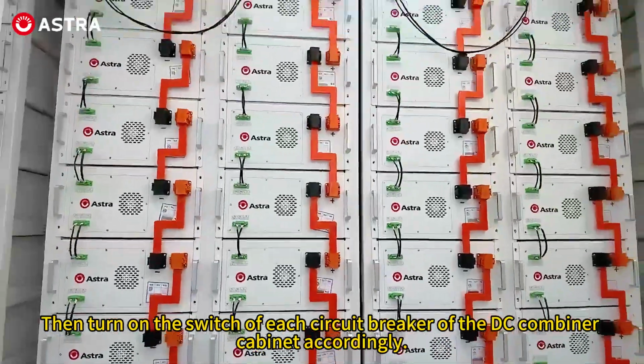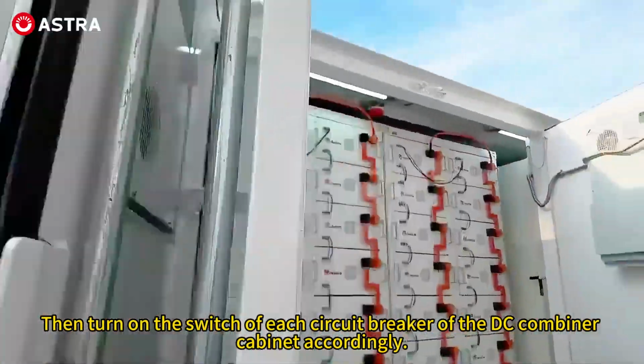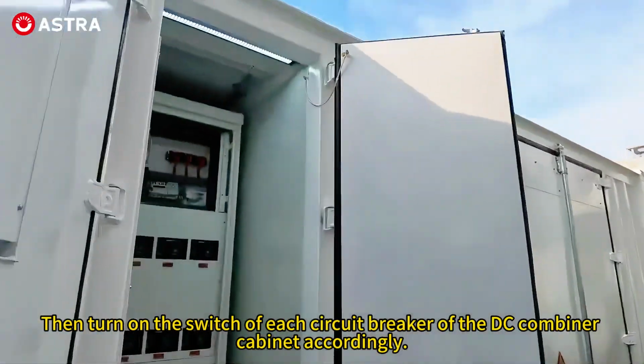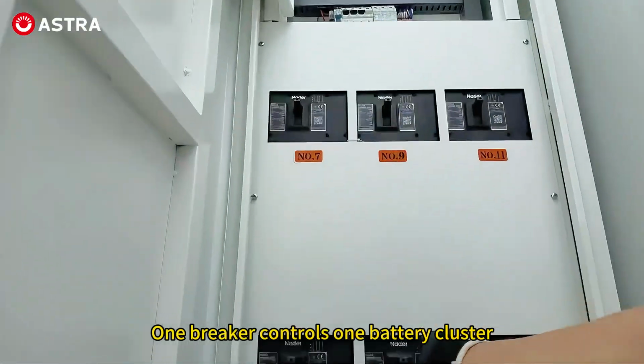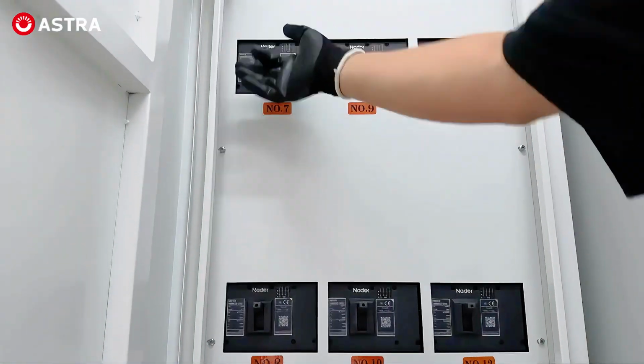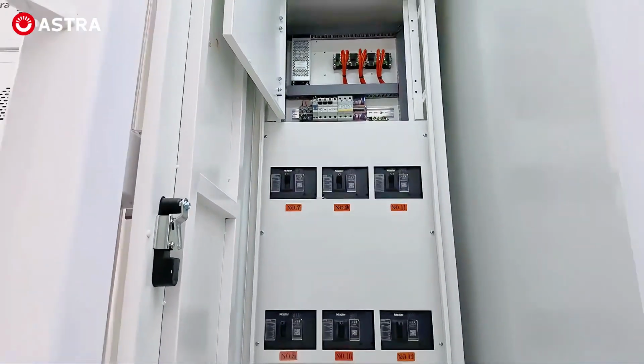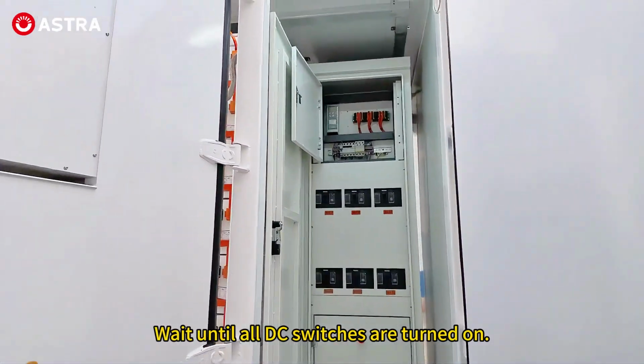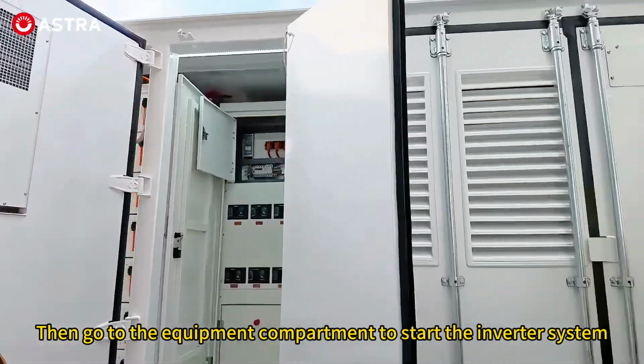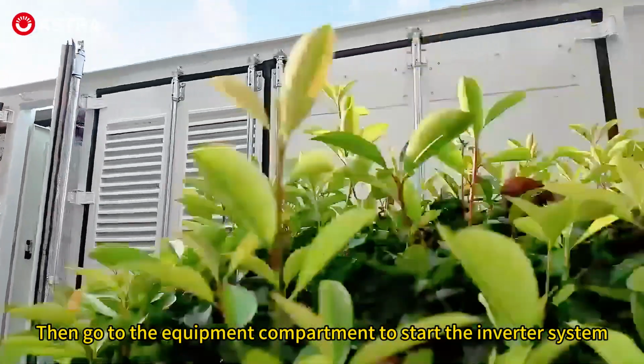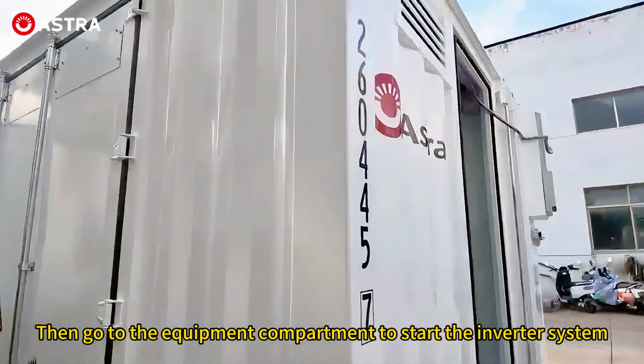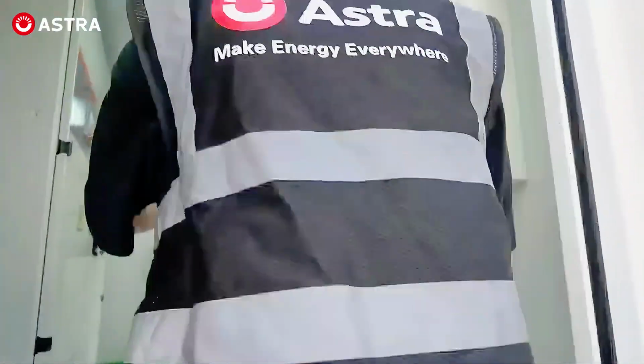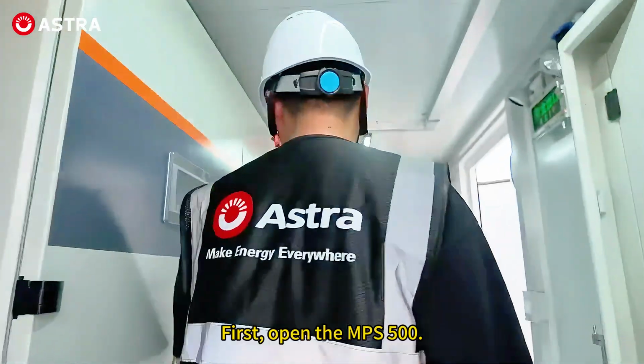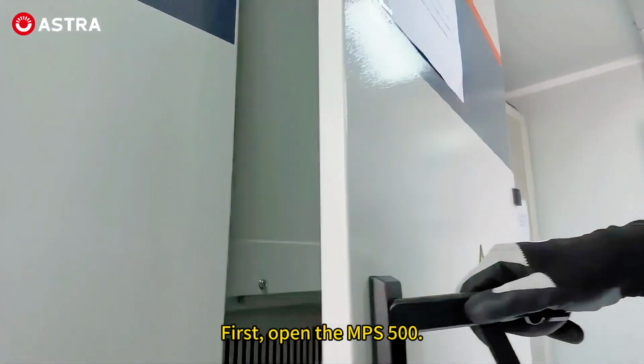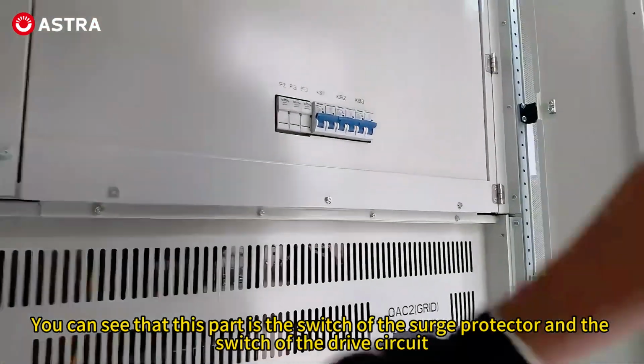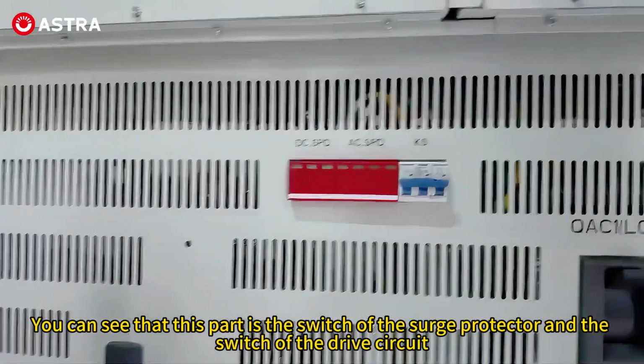Then turn on the switch of each circuit breaker of the DC combiner cabinet accordingly. One breaker controls one battery cluster. Wait until all DC switches are turned on. Then go to the equipment compartment to start the inverter system. First, open the MPS 500. You can see that this part is the switch of the surge protector and the switch of the drive circuit.